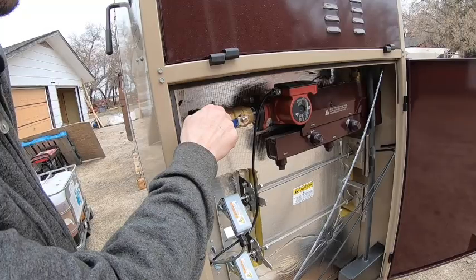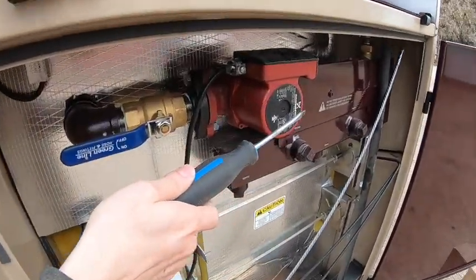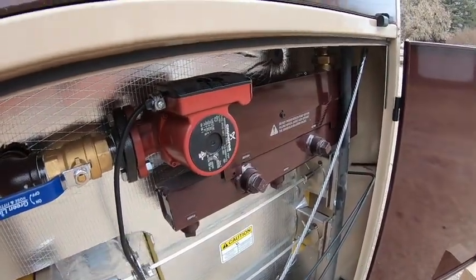This has boiler return protection, so it prevents too cold of water coming back, which can affect your secondary combustion. I'd like to ask you a question about that, because I never worried about that, but now with some of the newer stoves, that is a concern, right? You don't want water going to your house at 180 and coming back at 100 degrees. Is there a 30-degree difference in temperature that a guy should be looking at? Yeah, typically you don't want return water coming below 140. Okay. It alters the efficiency of the burn when you have too cold of water being sent back.